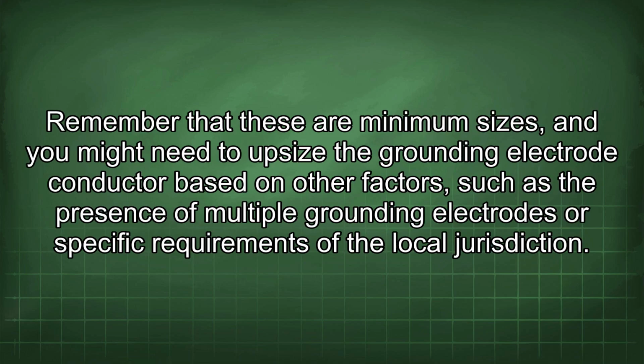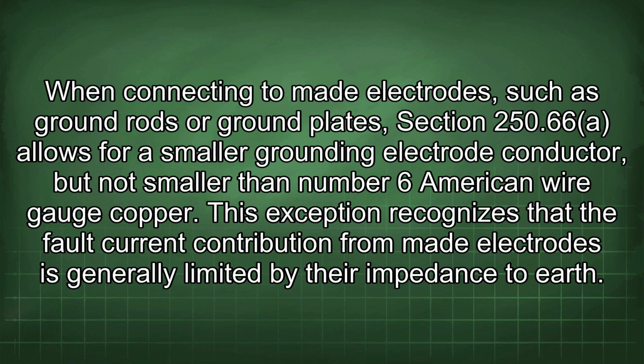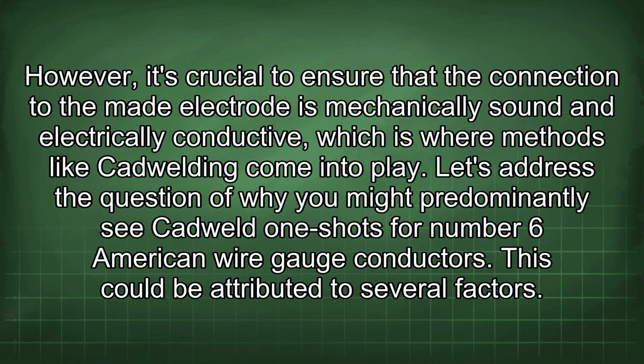Remember that these are minimum sizes, and you might need to upsize the grounding electrode conductor based on other factors such as the presence of multiple grounding electrodes or specific requirements of the local jurisdiction. When connecting to made electrodes, such as ground rods or ground plates, Section 250.66 allows for a smaller grounding electrode conductor, but not smaller than number 6 American wire gauge copper. This exception recognizes that the fault current contribution from made electrodes is generally limited by their impedance to earth. However, it's crucial to ensure that the connection to the made electrode is mechanically sound and electrically conductive, which is where methods like Cadwelding come into play.